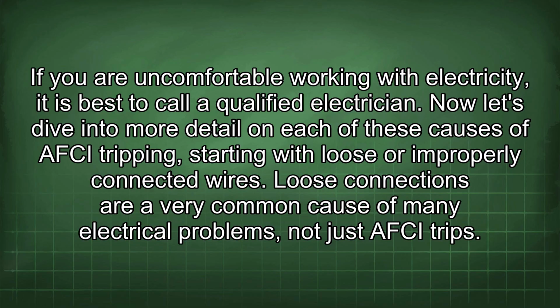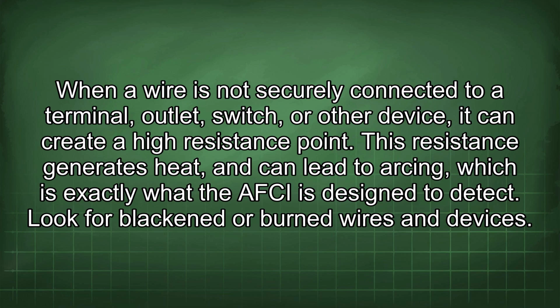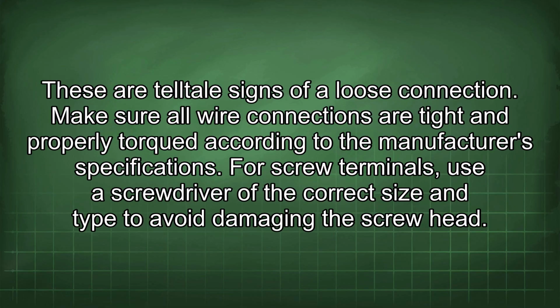Now let's dive into more detail on each of these causes of AFCI tripping, starting with loose or improperly connected wires. Loose connections are a very common cause of many electrical problems, not just AFCI trips. When a wire is not securely connected to a terminal, outlet, switch, or other device, it can create a high resistance point. This resistance generates heat and can lead to arcing, which is exactly what the AFCI is designed to detect. Look for blackened or burned wires and devices. These are telltale signs of a loose connection.